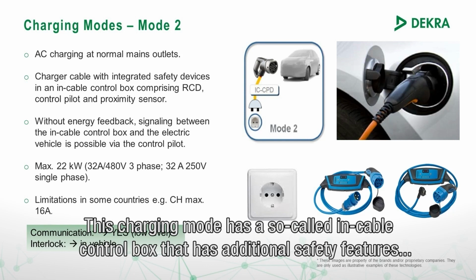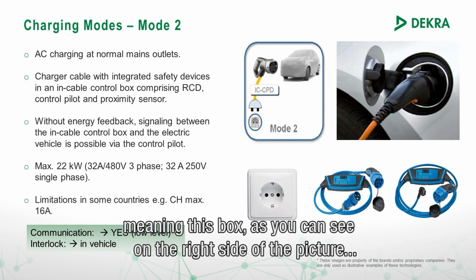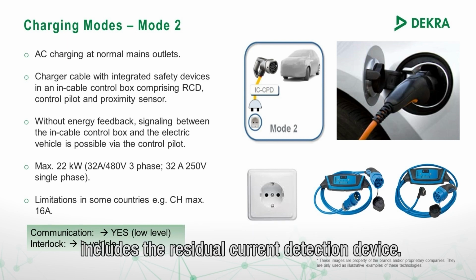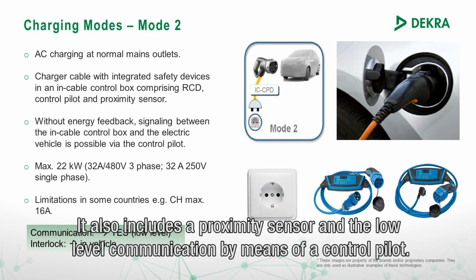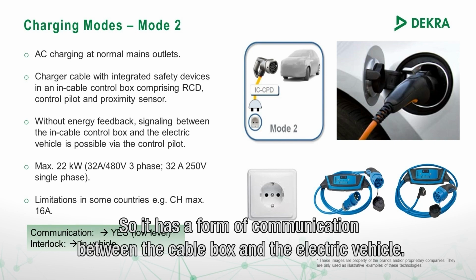This charging mode has a so-called in-cable control box with additional safety features. This box, as you can see on the right side of the picture, includes the residual current detection device, a proximity sensor, and low-level communication by means of a control pilot - a form of communication between the cable box and the electrical vehicle.